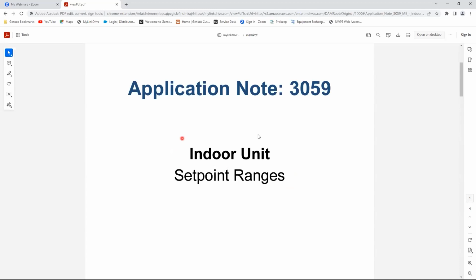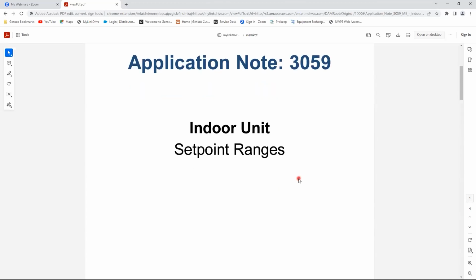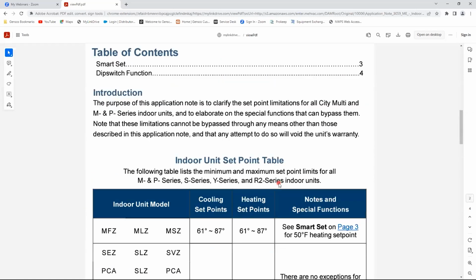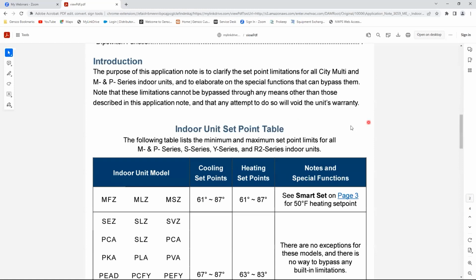Okay. So when you plug that in, it reads the indoor unit information, and what is programmed into the board is what that thermostat will go down to. Even though the instructions say 50 degrees, there are a couple of units in Mitsubishi land that will go down to a 50-degree heating set point, not cooling. 63 is the lowest. So we come down here, 61 is the lowest. So if we come down here, the indoor unit set point table gives us the indoor unit model number, and it gives us cooling set points and heating set points. 61 to 87 is our set point range for heating and cooling on these 3 units.